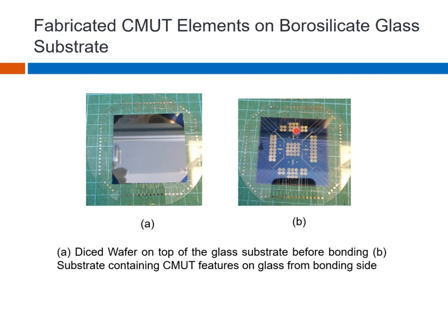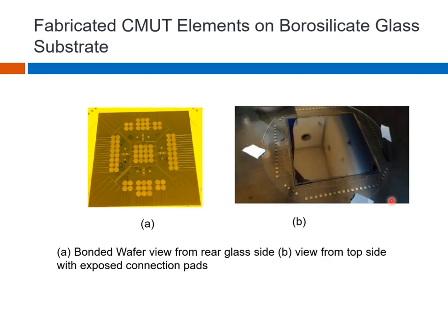Yeah, this is on the rear side. You can see those CMUT circular radiators, which have a diameter of about 2.8 mm. So those are large scale features. Yeah, but okay. So this is before bonding. But after bonding, this looks like something like this.